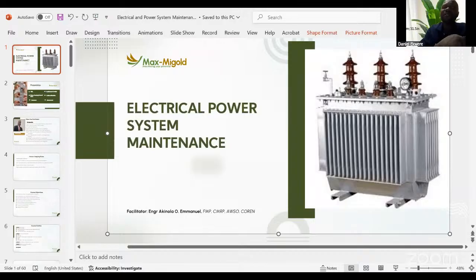That means we had been underloading the genset, when what we needed would have been, say, 200 kVA, which would have been fine for the load. But we were running 500 kVA with a load not even up to 20% of capacity, which is very bad for genset operation. So that is why predictive maintenance is very useful, because it gives accurate information and lets you take a pre-informed decision for the future.